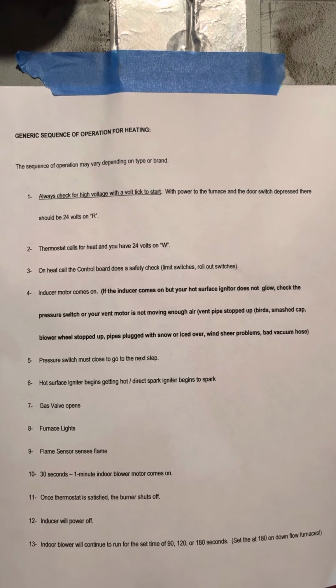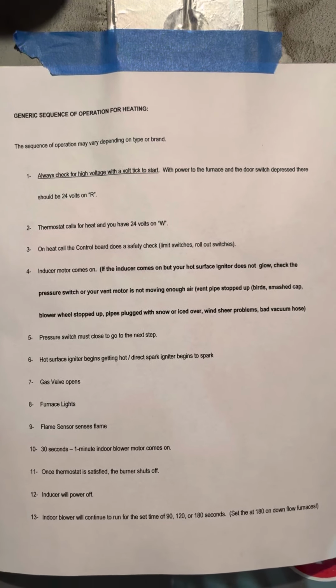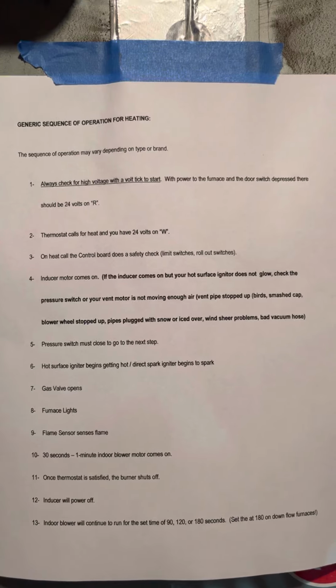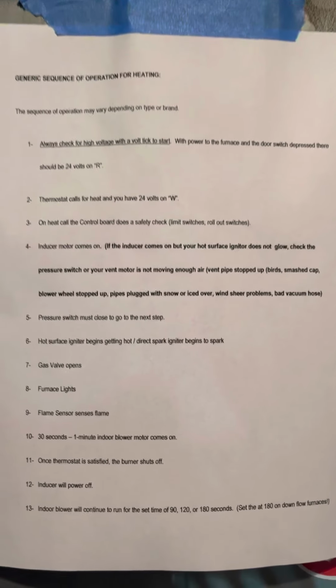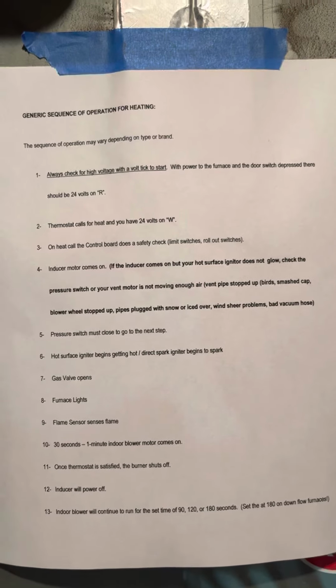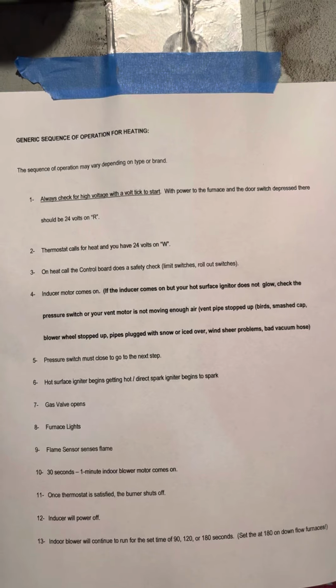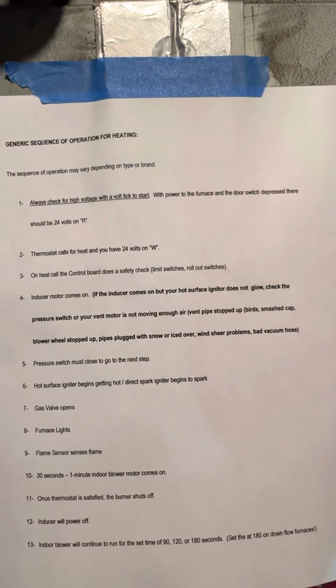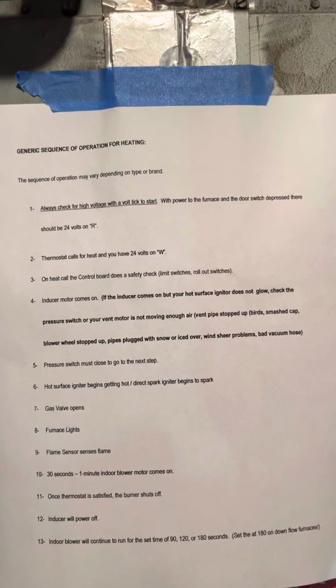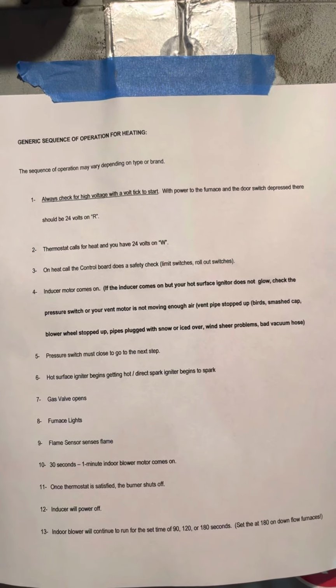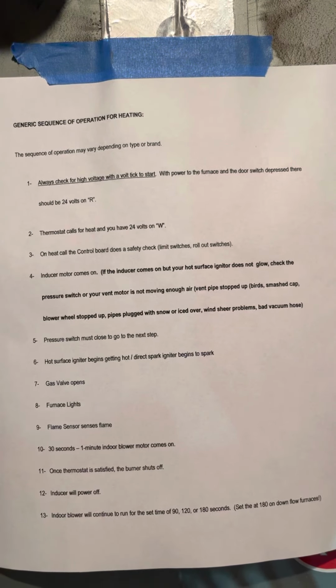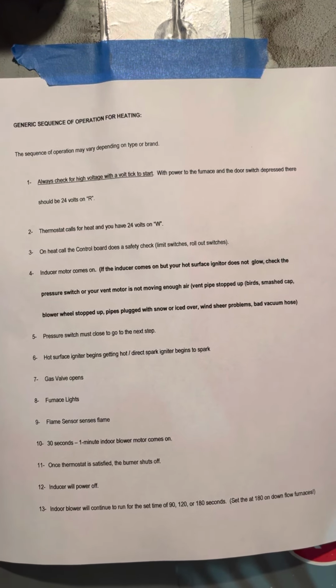So once you have 120 volts coming into the furnace, the control board is going to send 24 volts out on R, and the thermostat will send 24 volts back to the furnace on W on a call for heat, and then the integrated control board is going to do a safety check. It'll check the limits to see if the limits are open and the rollouts are open, and then it'll start the inducer. The inducer will pull a negative draft on the pressure switch.